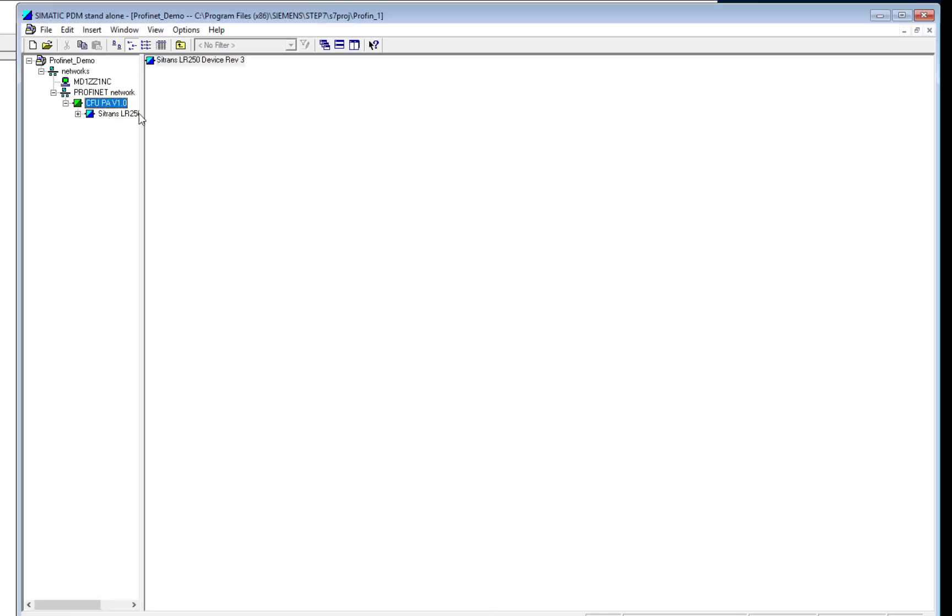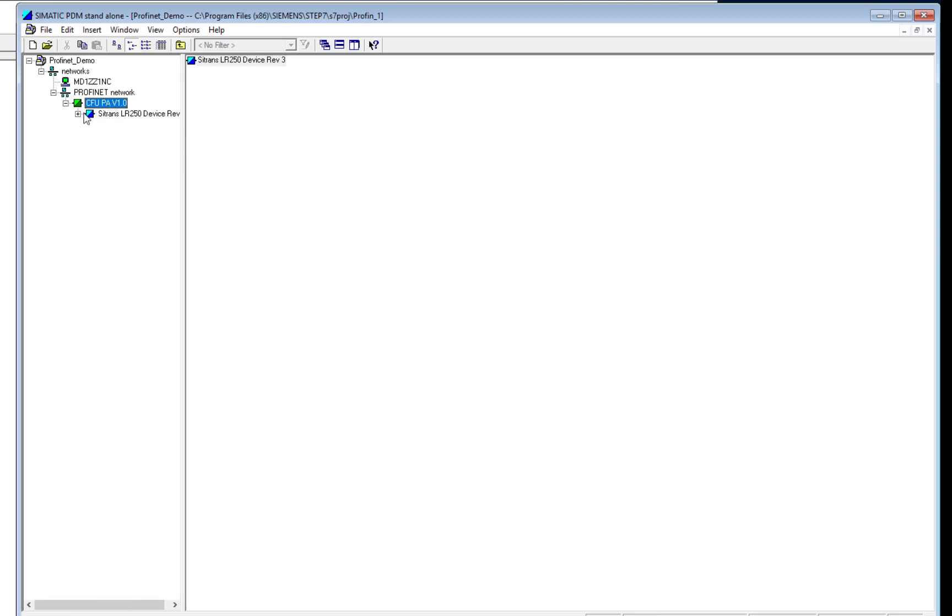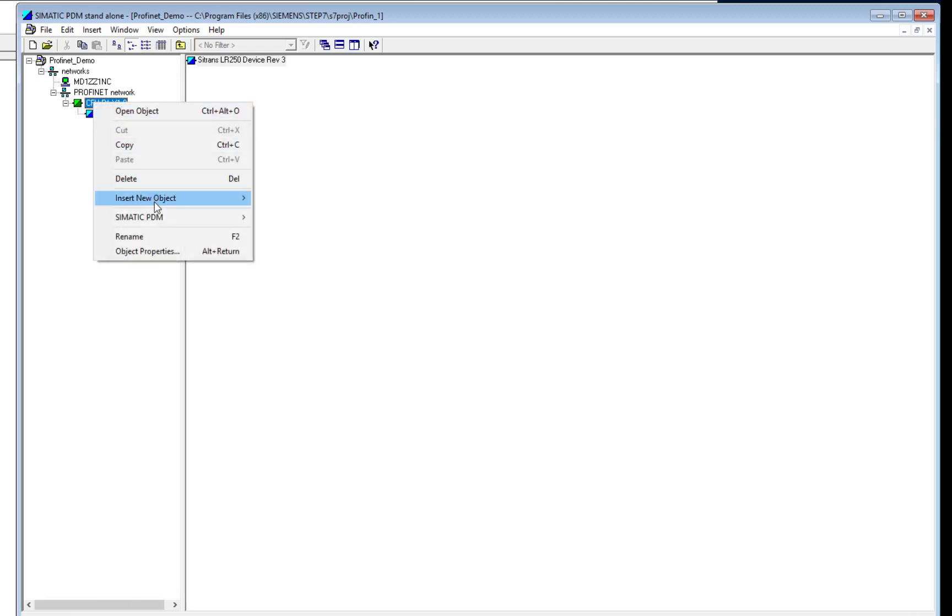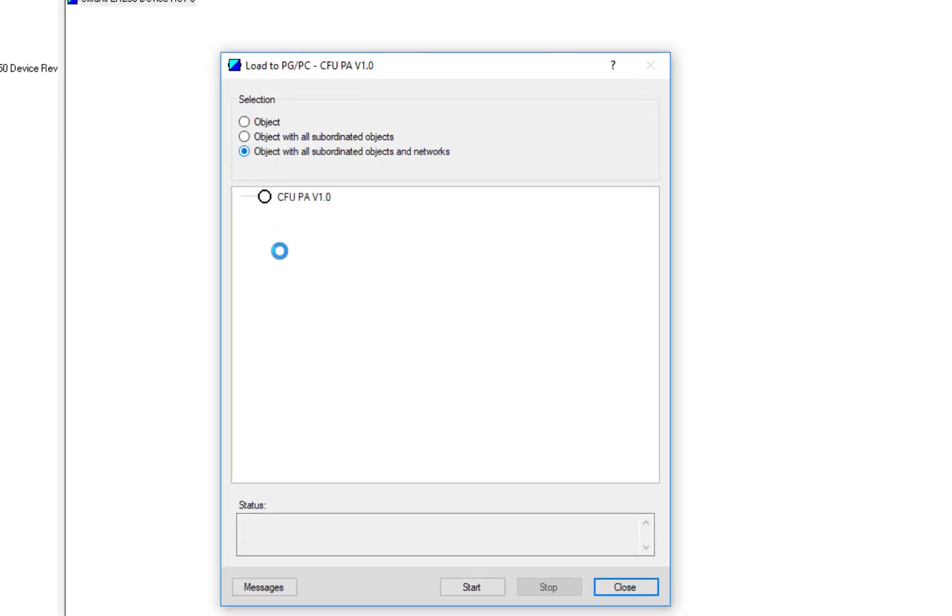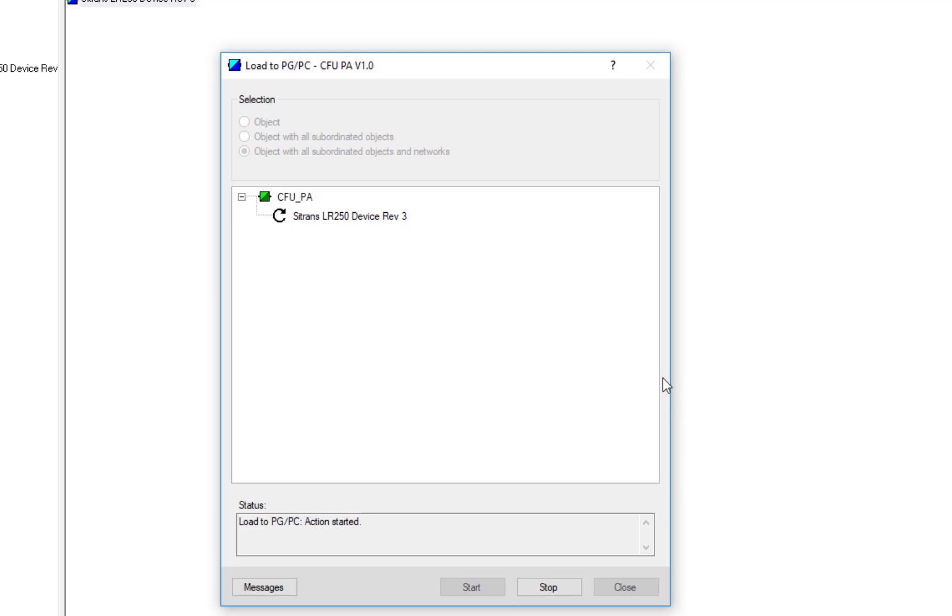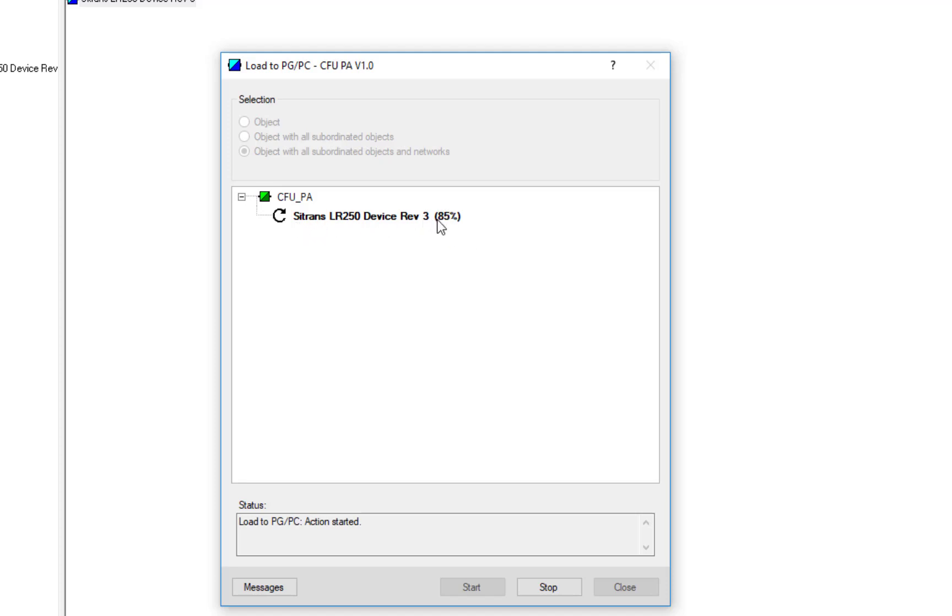So what I can do now is right-click on the very top, PDM, I want to load the device parameters to this project. So we're going to load to the PC, we'll select the subnets, so not just the Compact Field Unit, and this will read all of the devices. In this case, it's just one. If we had eight devices, it would read the parameters from eight devices. If you ever used PDM before on Profibus PA, please note the speed that this is uploading. It's vastly faster than a standard Profibus DP to PA connection, so it can help with your commissioning times.